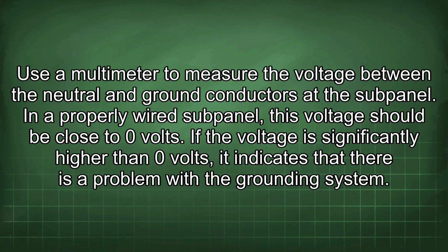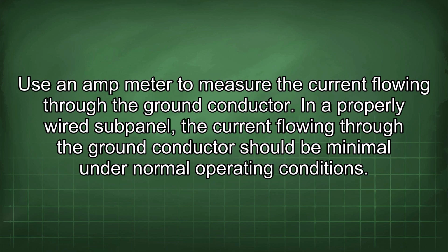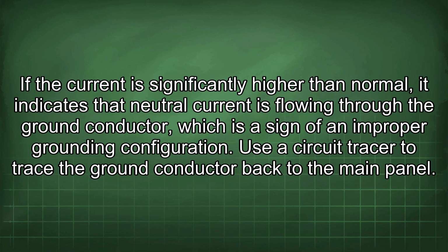Use a multimeter to measure the voltage between the neutral and ground conductors at the subpanel. In a properly wired subpanel, this voltage should be close to 0 volts. If the voltage is significantly higher than 0 volts, it indicates that there is a problem with the grounding system. Use an ammeter to measure the current flowing through the ground conductor. In a properly wired subpanel, the current flowing through the ground conductor should be minimal under normal operating conditions. If the current is significantly higher than normal, it indicates that neutral current is flowing through the ground conductor, which is a sign of an improper grounding configuration.